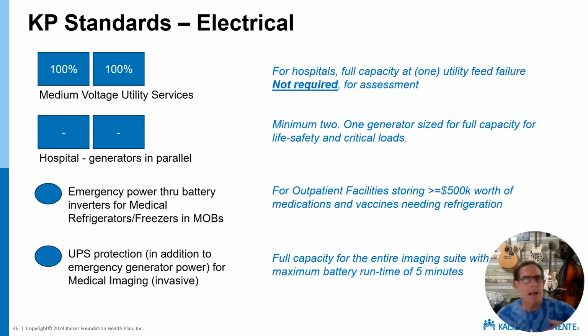For electrical, we ask our design teams to look at 2 medium voltage services, but that is not really a requirement. That's something for economic consideration. I'll show you an example of that in a second. We do require at least 2 generators on the hospital, and we have it sized so that if one were to fail, we would still meet critical and life safety.